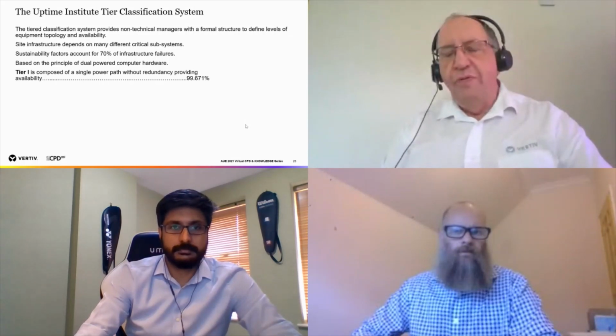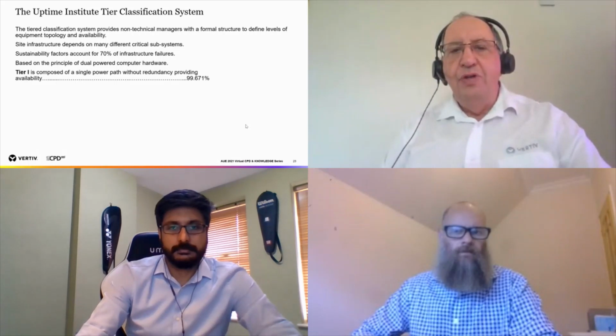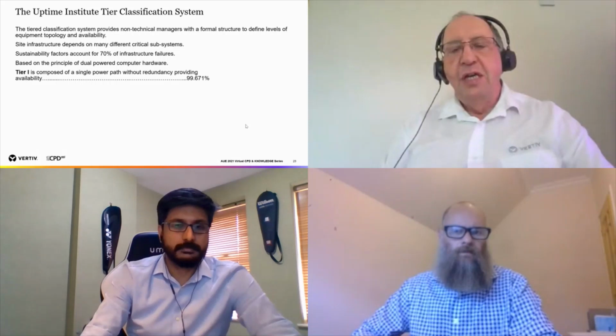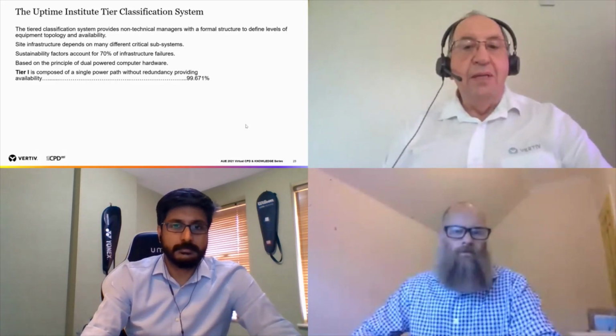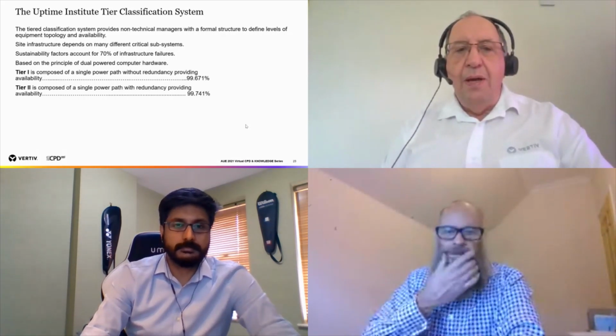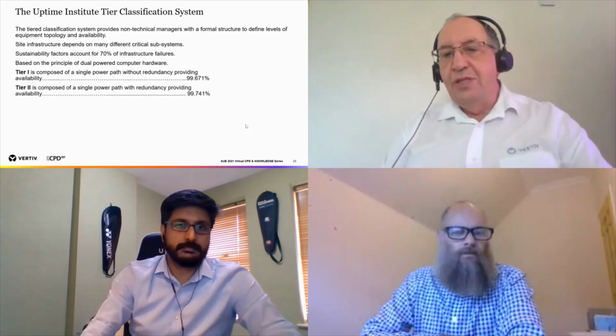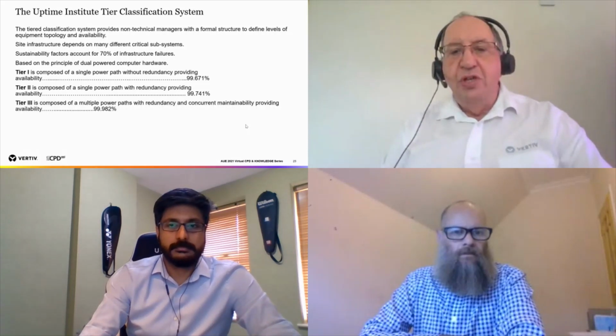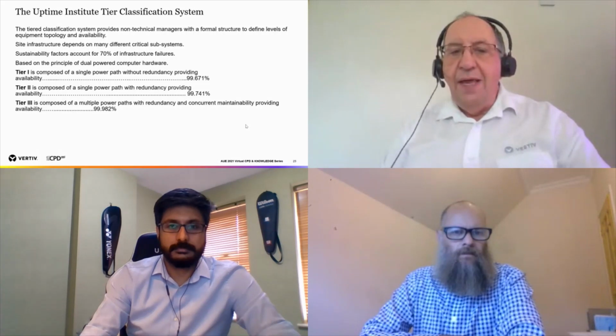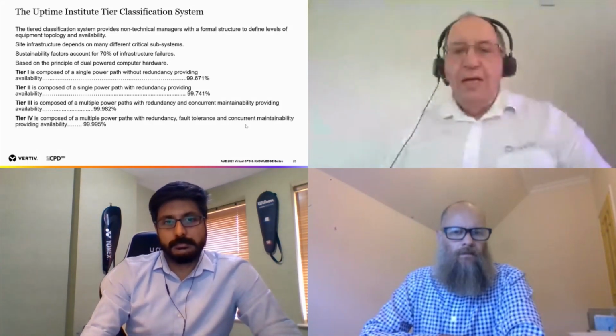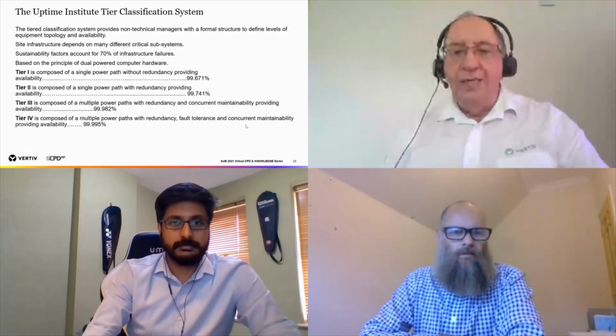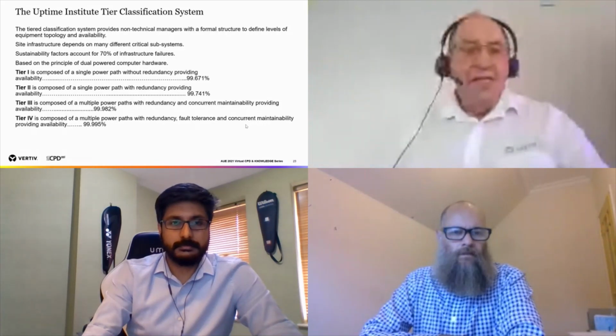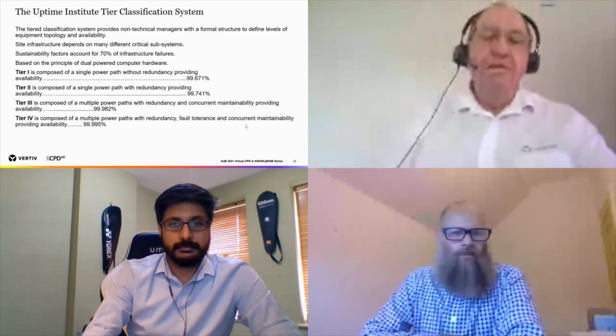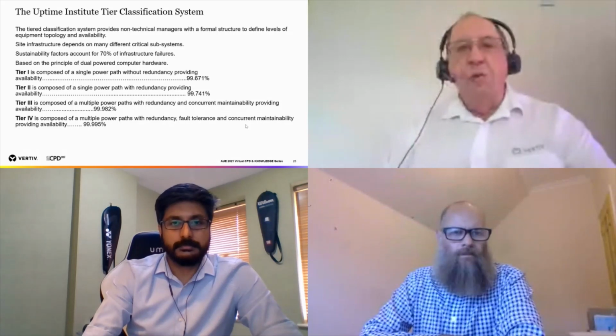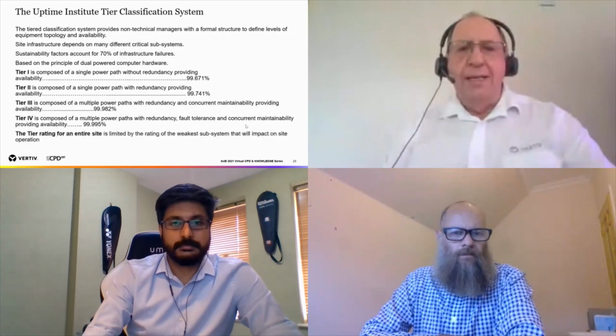So tier 1, which is what we've just been looking at, is a single power path without redundancy, and that gives us 99.671% availability. Tier 2 is a single power path with redundancy, giving us 99.741. Tier 3 is redundancy with concurrent maintainability, and that now gives us 99.9% availability. And then tier 4 gives us redundancy, fault tolerance, and concurrent maintainability, and that gives us 99.99, and that's where 4 nines comes from. You've probably heard 4 nines being offered by people as a way of designing a system. But what does that really mean in practice?